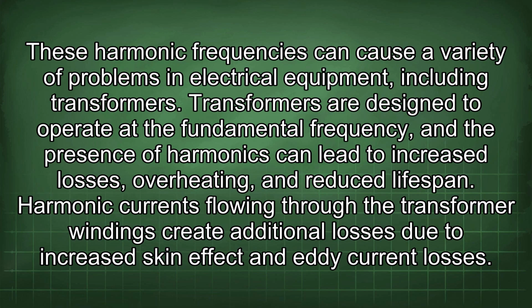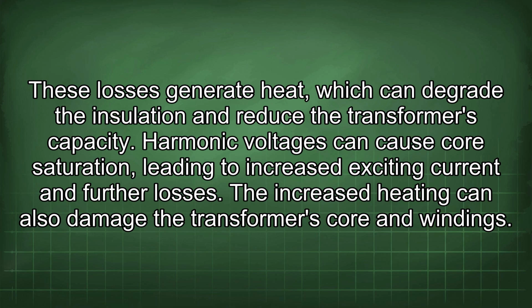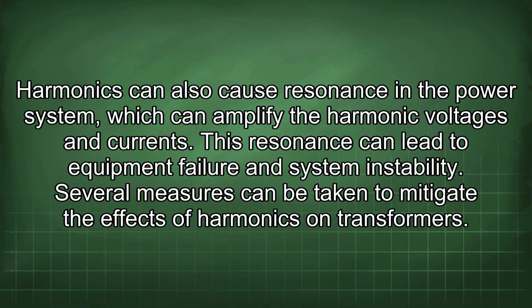and reduced lifespan. Harmonic currents flowing through the transformer windings create additional losses due to increased skin effect and eddy current losses. These losses generate heat, which can degrade the insulation and reduce the transformer's capacity. Harmonic voltages can cause core saturation, leading to increased exciting current and further losses. The increased heating can also damage the transformer's core and windings. Harmonics can also cause resonance in the power system, which can amplify the harmonic voltages and currents. This resonance can lead to equipment failure and system instability.